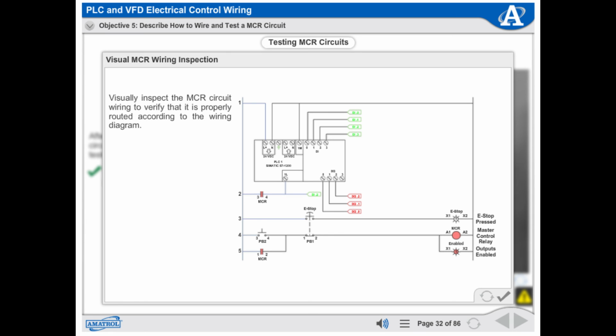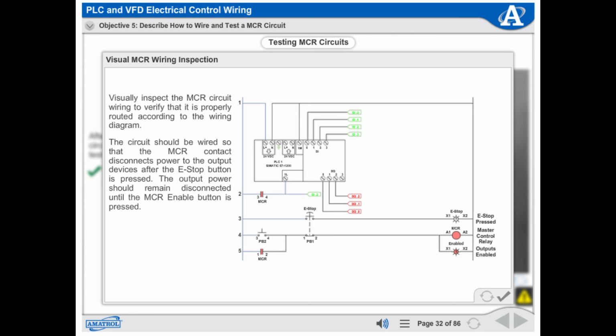Visually inspect the master control relay circuit wiring to verify that it is properly routed according to the wiring diagram. The circuit should be wired so that the master control relay contact disconnects power to the output devices after the E-stop button is pressed. The output power should remain disconnected until the master control relay enable button is pressed. Make sure the wires are properly terminated to all devices in the master control relay circuit.